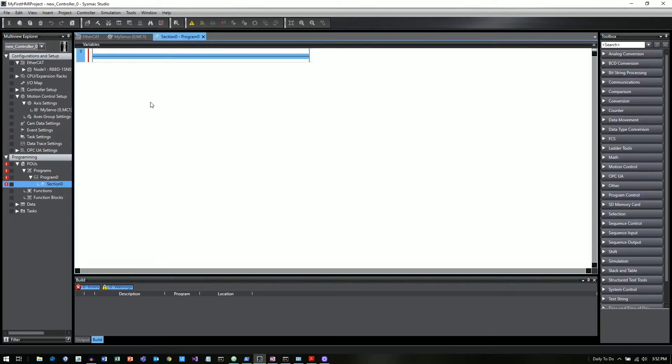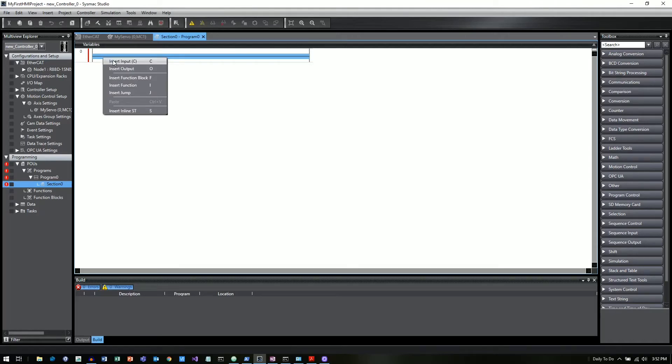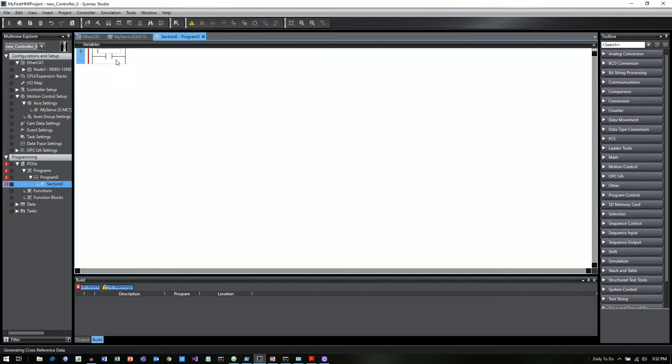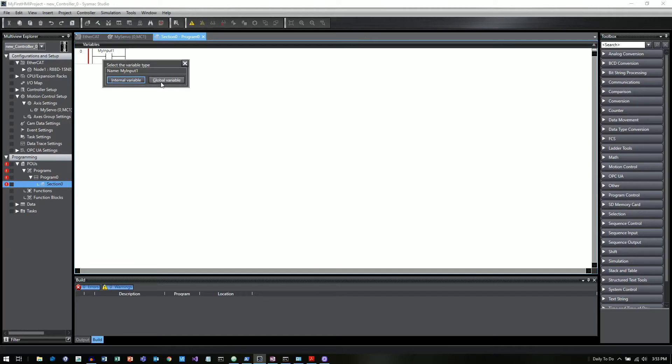Now what I want to do is go into your project and we're going to just do some real basic examples here and then show how to pull that into an HMI. So one thing we want to do is you can either click create a contact right on the rung. So you can either do that by hitting a right click on the rung and then hitting insert input and I'll put a just a my input 1 and one of the settings you can set up in Sysmac Studio is to ask you each time if you want it to be an internal or a global variable. If this is a variable that you want to have available to the HMI, you need to make sure that that shows as a global variable.